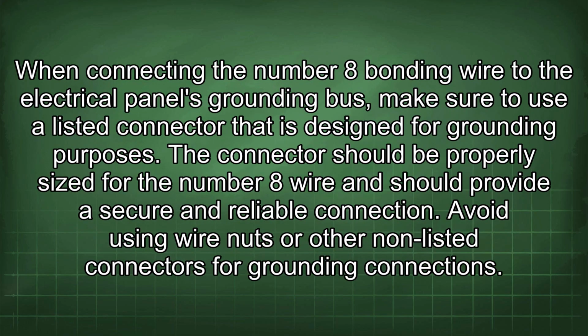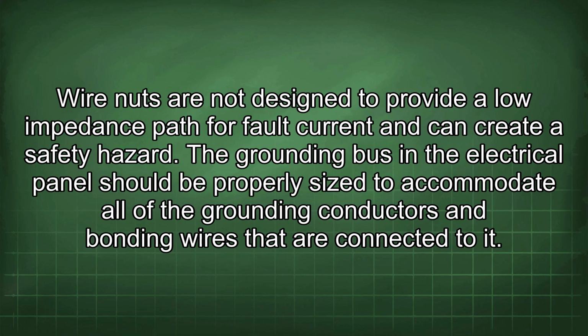When connecting the number 8 bonding wire to the electrical panel's grounding bus, make sure to use a listed connector that is designed for grounding purposes. The connector should be properly sized for the number 8 wire and should provide a secure and reliable connection. Avoid using wire nuts or other non-listed connectors for grounding connection. Wire nuts are not designed to provide a low impedance path for fault current and can create a safety hazard.